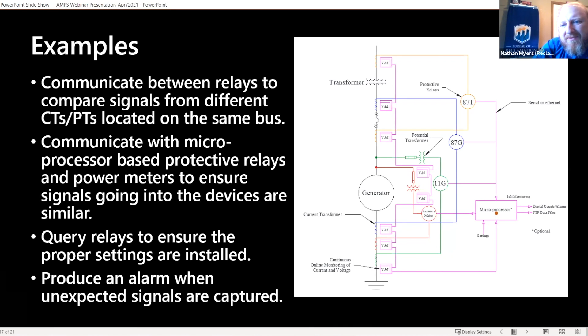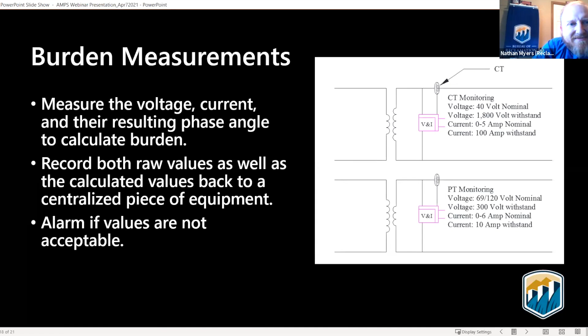If we look at burden measurements, just as an example, we want to be able to measure the voltage, current, and the resulting phase angle to be able to calculate the burden on the CTs and PTs. We want to record both raw values as well as the calculated values back at a centralized piece of equipment. If the values are not within an acceptable tolerance or range, we want to be able to alert the folks in the field that there may be an issue with their protective system. And that's what I have with the Bureau of Reclamation.